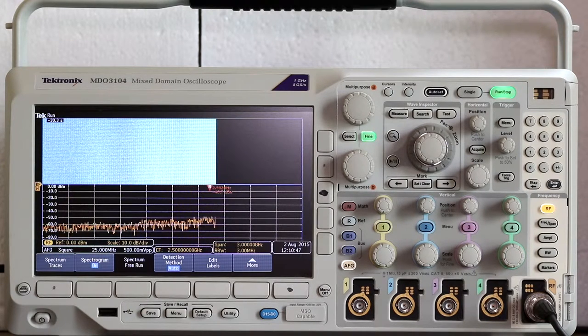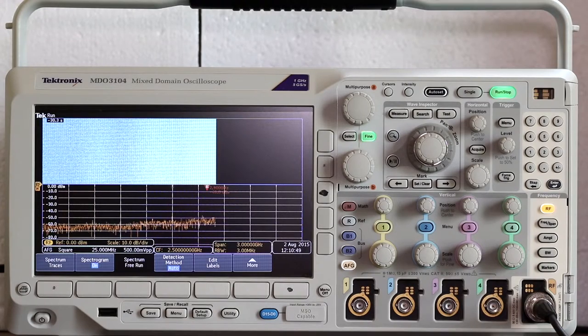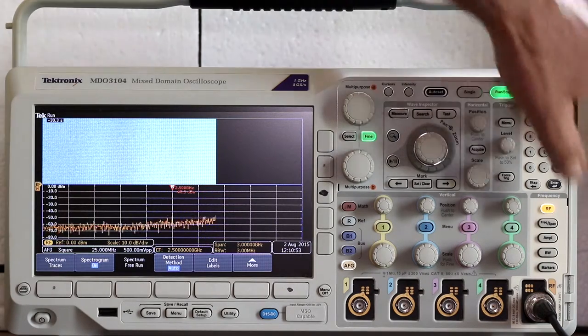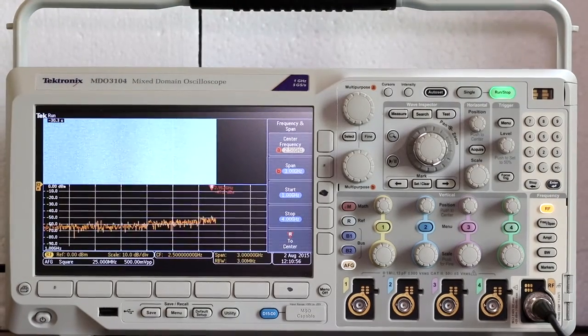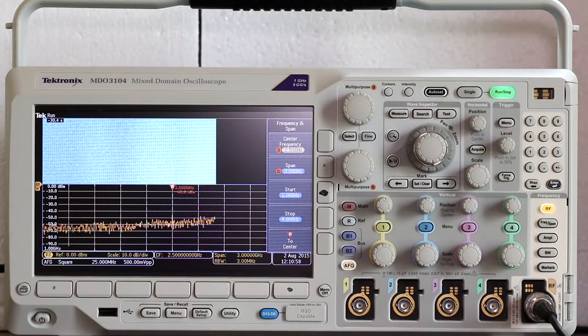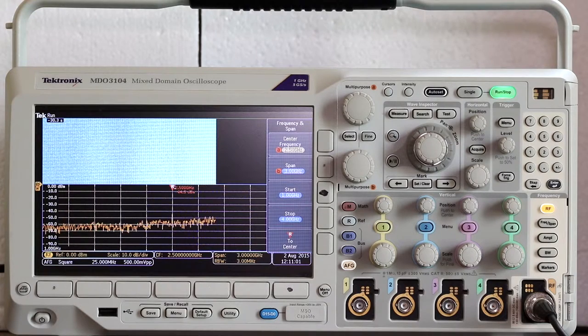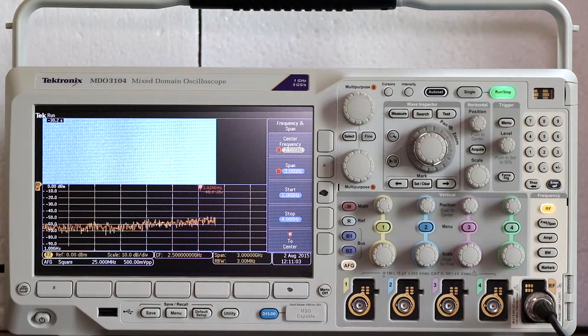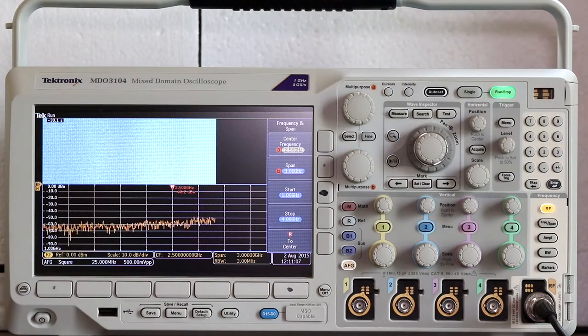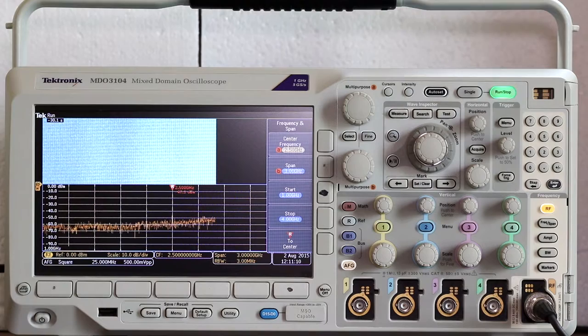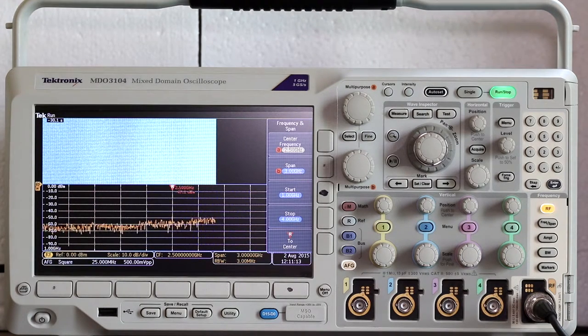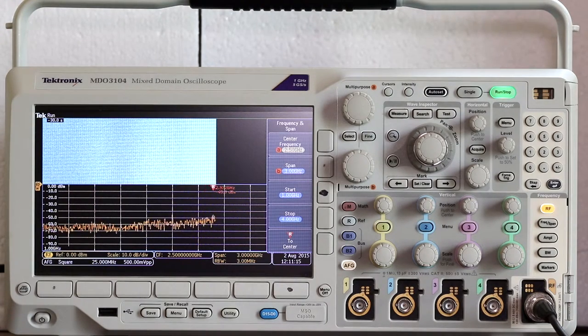This is a little easier to see if you press span, just below RF. The vertical frequency and span menu comes up, and you can press the bottom soft key, currently labeled To Center. That shifts the fundamental to the center of the display, making everything more readable.